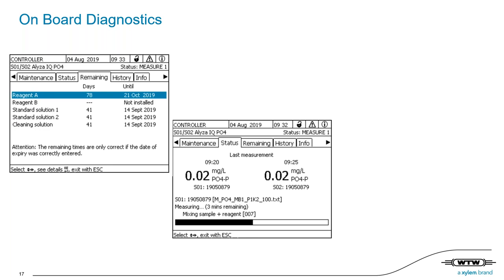Natalie, the last question I have on the list is, can we use the Alyza to measure total phosphorus? It's orthophosphate only, but I know that in a lot of treatment plants, you have a more or less stable factor between orthophosphate and total phosphorus, so you can do the calculation in your PLC, for example, afterwards. But the analyzer itself measures only PO4-P or PO4, depending on the measurement.